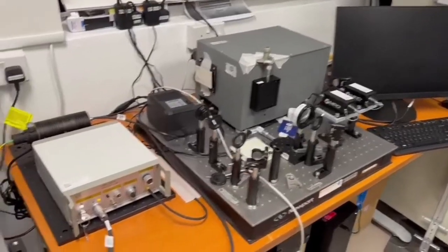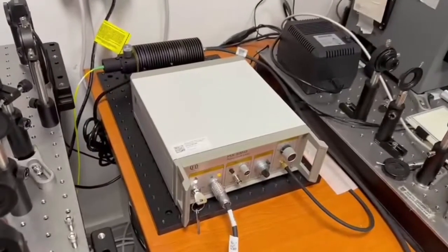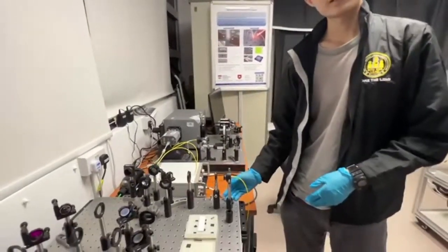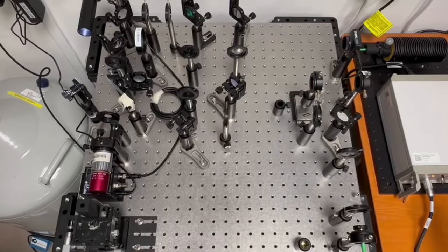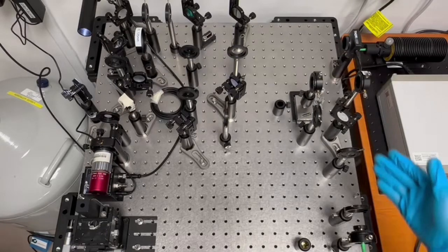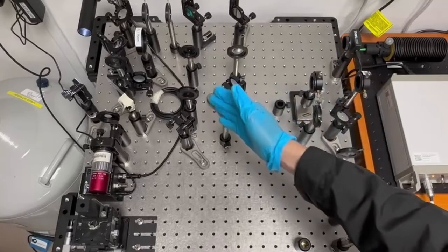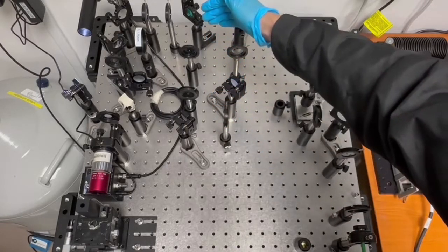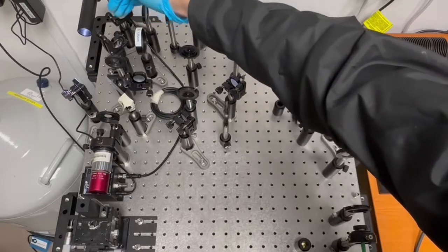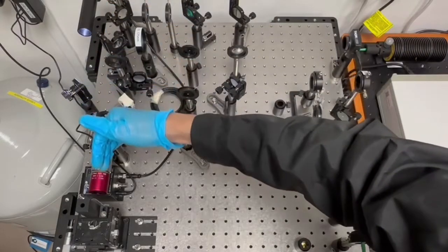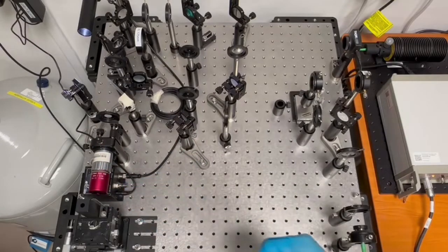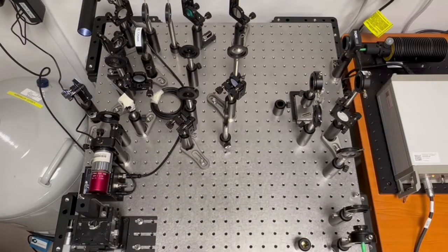From the lasing compartment, we have this pulse pump laser, which is fiber connected to the sample compartment. The pulse laser is first connected to this fiber collimator, where it passes through this series of mirrors onto a dichroic mirror, and it will reflect the 532 nanometer beam down this path onto this objective lens, converging the pulse laser onto a sample.